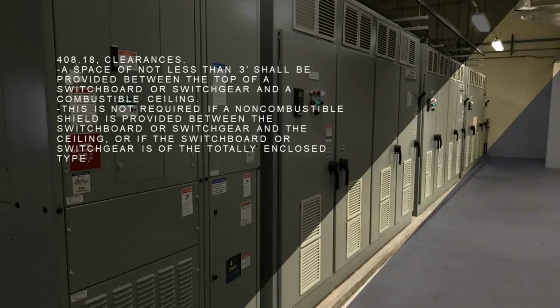All right. So spaces and clearances. This was a little bit of a change in the 23 as well. So 408.18 clearances. A space of not less than 3 feet shall be provided between the top of a switchboard or switchgear and a combustible ceiling. This is not required if a non-combustible shield is provided between the switchboard or switchgear and the ceiling, I apologize, or if the switchboard or switchgear is of the totally enclosed type. So if it's totally enclosed, not really a big deal. I've seen open ones, but most of the open ones I've seen are DC switchboards and panel gear.